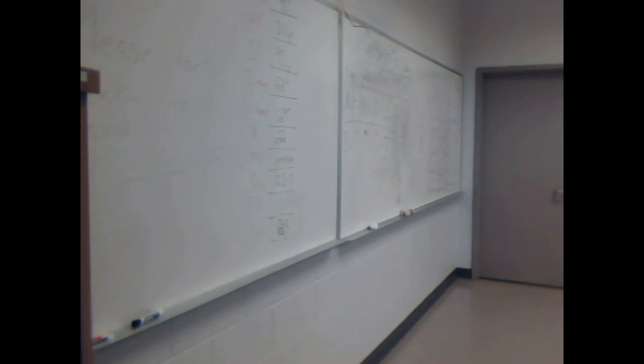All right, liquid. I'm not worried about liquid at all. Y'all may occasionally run over somebody who's got a well or a pond, but for the most part, we don't do liquid, right? Almost all your equipment is air. All right, now, so the main thing here I'm looking for is, for some reason, we're having one of those symptoms, okay, and it's because of the air quantity going over the coil. And the way to check it is the temperature, right? And if it's outside of that range, we got a problem.